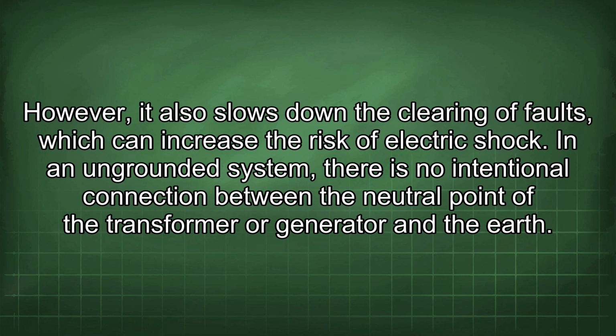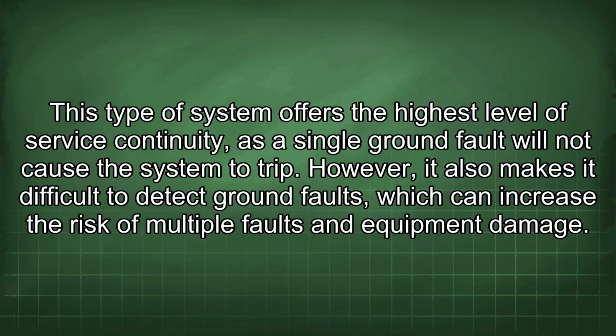In an ungrounded system, there is no intentional connection between the neutral point of the transformer or generator and the earth. This type of system offers the highest level of service continuity, as a single ground fault will not cause the system to trip. However, it also makes it difficult to detect ground faults, which can increase the risk of multiple faults and equipment damage.